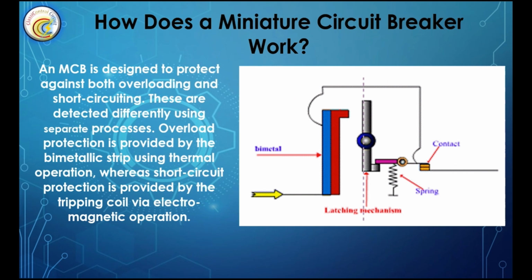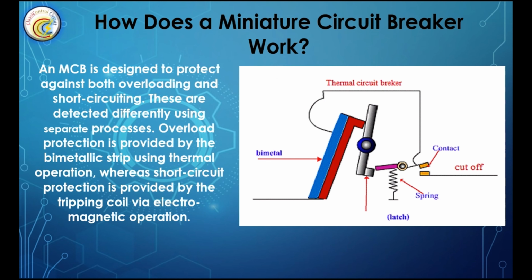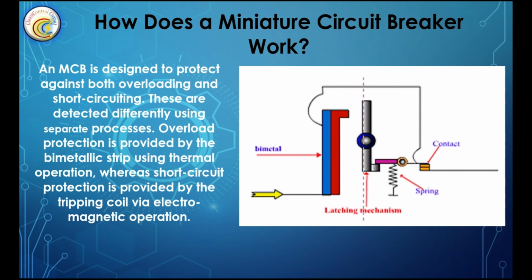Excess current causes the bimetallic strip within the MCB to heat, bend, and trip. This releases a switch which moves the electrical contact points apart to confine the arc. The arc is divided and cooled by an insulated metal strip called the arc chute. The contacts close again once the fault has been fixed and the MCB is reset.